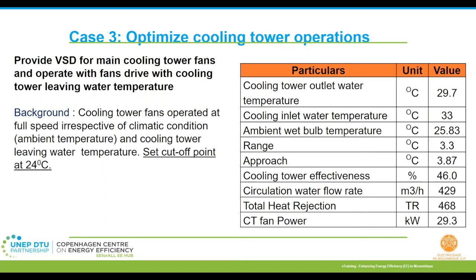The intention was good, but the fundamental approach was flawed, because as per the ambient atmospheric conditions, the wet bulb temperature is itself about 25 to 26 degrees centigrade. So it would be practically impossible for the cooling water to reach 24 degrees in the first place. You should know that through the concept of evaporative cooling, the water temperature cannot go lower than the wet bulb temperature.